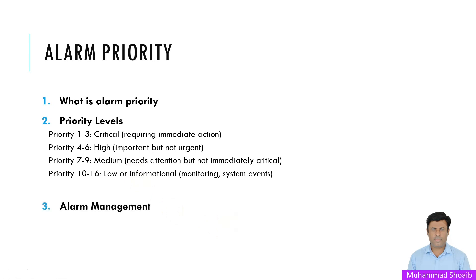Alarm management priority allows operators to quickly assess the situation by filtering or sorting alarms based on their importance. In HMI or SCADA systems, alarms with high priority — like in Siemens WinCC — may trigger more visible or audible notifications such as a flashing red on the screen or a sound alarm horn, while low-priority alarms might only appear in the background.